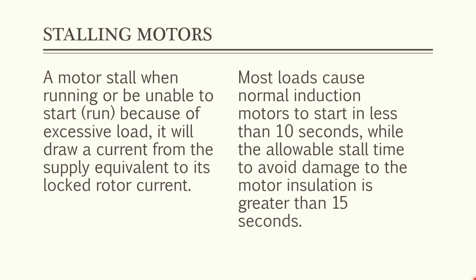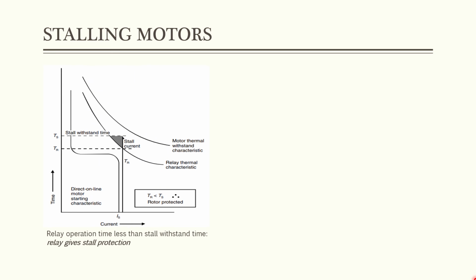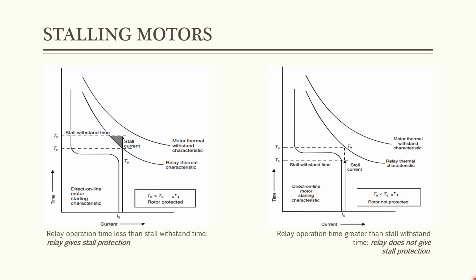Most loads cause normal induction motors to start in less than 10 seconds, while the allowable stall time to avoid damage to the motor insulation is greater than 15 seconds. So this is the first graph, where the relay can give stall protection, and the condition is that the relay operation time must be less than the stall withstand time. And this is the graph for the relay where it no longer can give stall protection, when the condition is that relay operation time is greater than the stall withstand time.